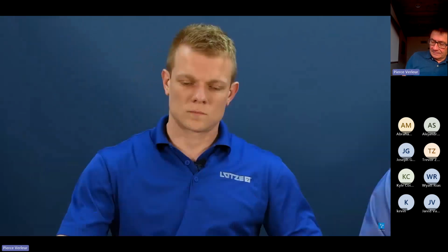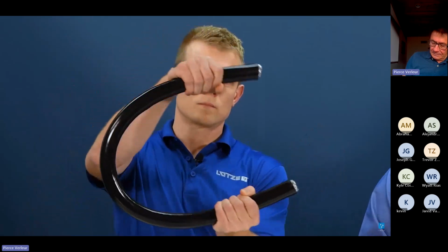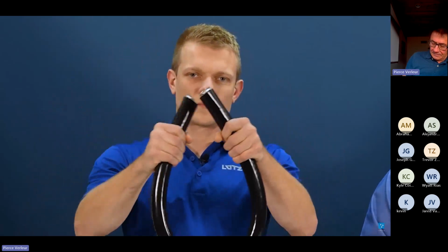It's also known that VFD applications create a lot of high voltage spiking. Therefore, we use an XLPE insulation on the conductor that helps to cope with those spikes. The XLPE material offers great electrical values and voltage breakthrough resistance. In addition, DriveFlex is the most flexible drive cable on the market.